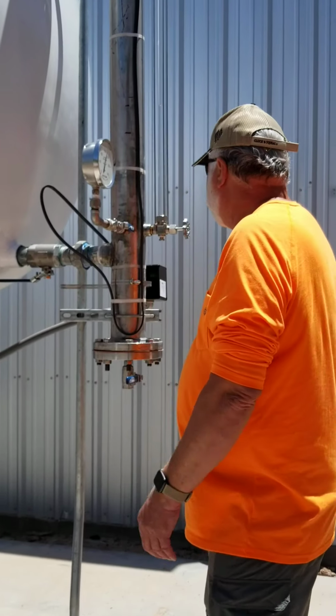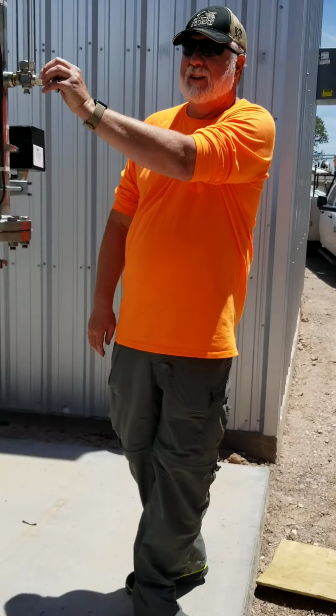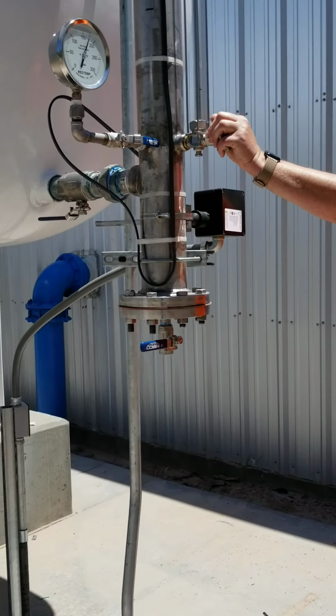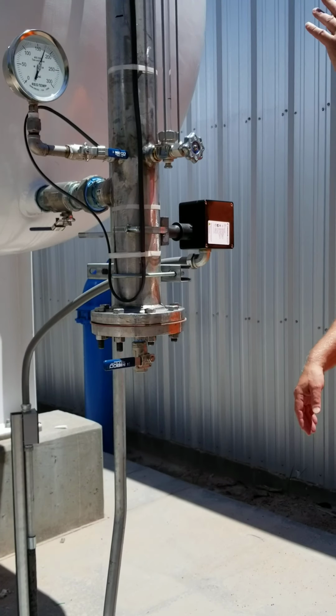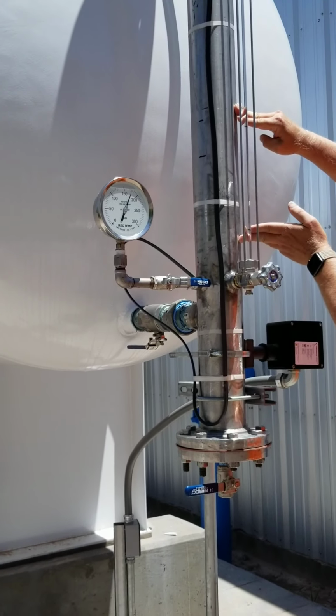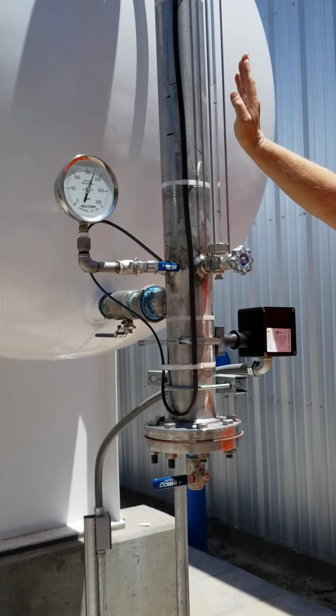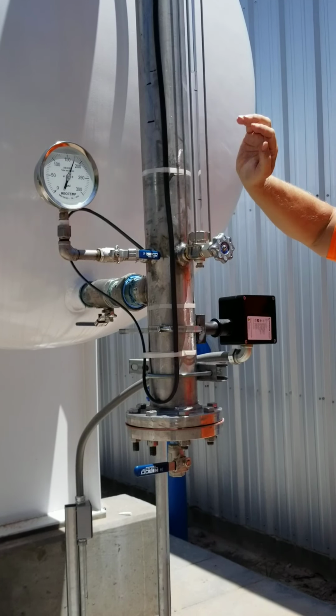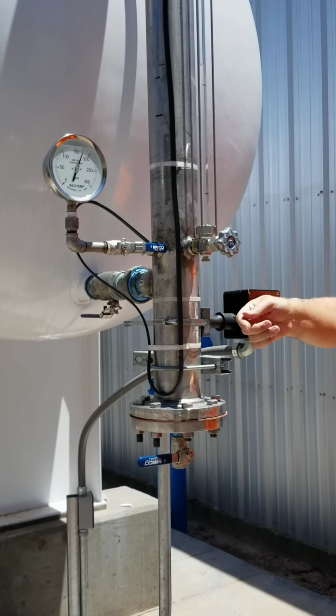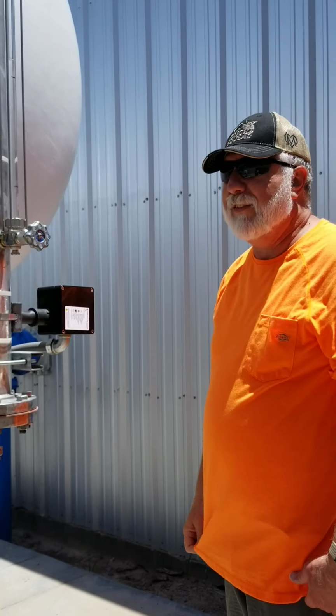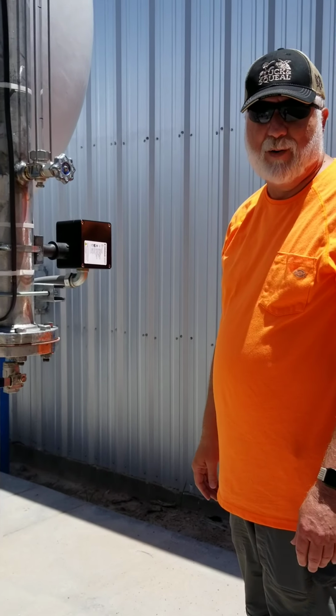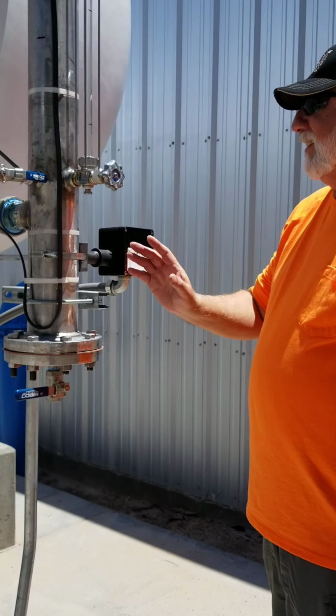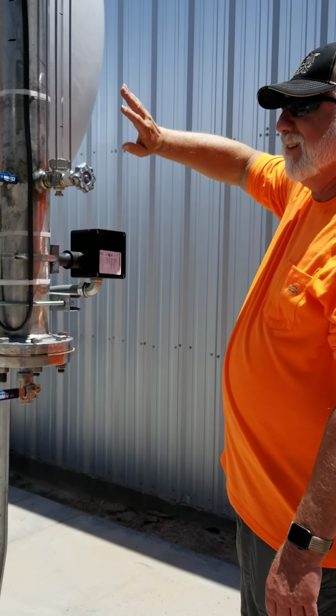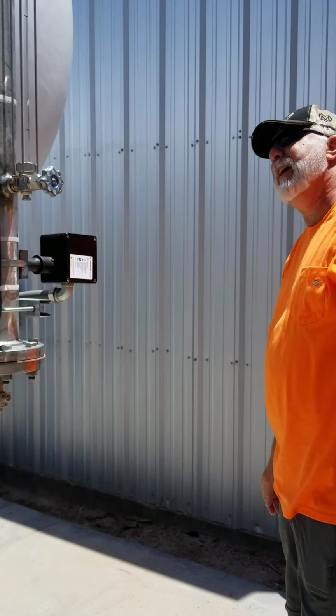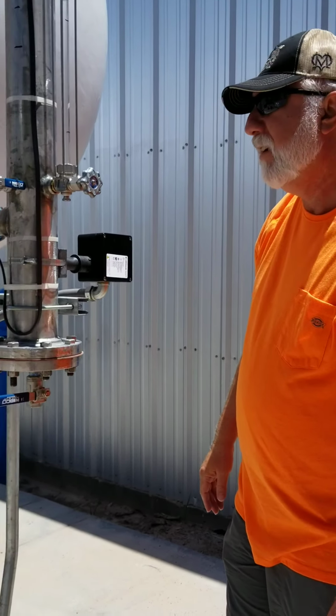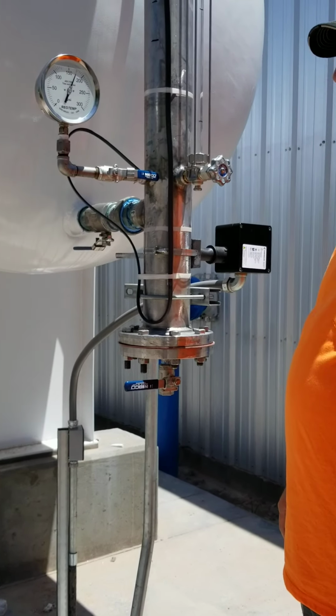I would suggest this sight glass is here just as a manual indication. If you come up, you can take a quick look and see, yes, it's within the proper range. In the winter, obviously when it's going to freeze, close these valves, top and bottom, and drain it. I get calls every year that the glass is broken. Exactly, because this has nothing to do with the operation of the system. This is just so you can walk up and go, yep, that looks good. Can they heat trace that also? They can. It is heat traceable.